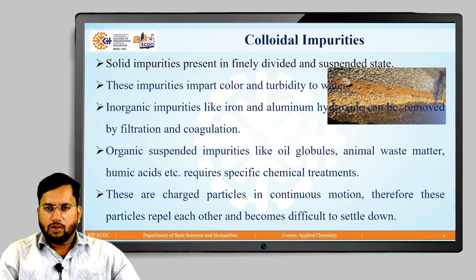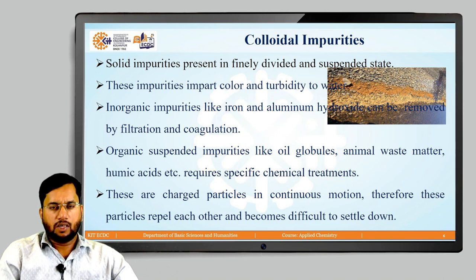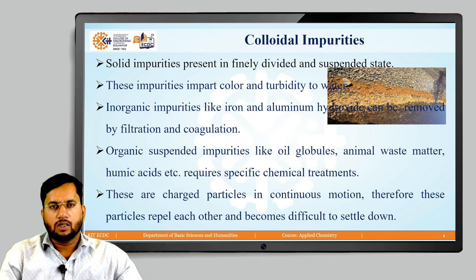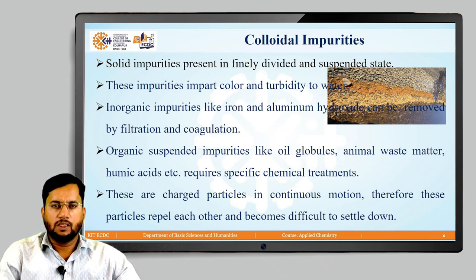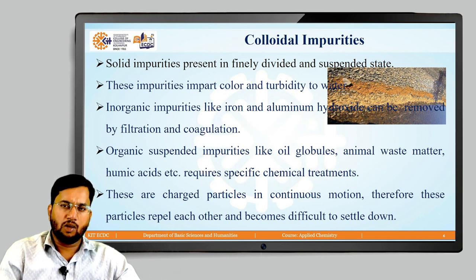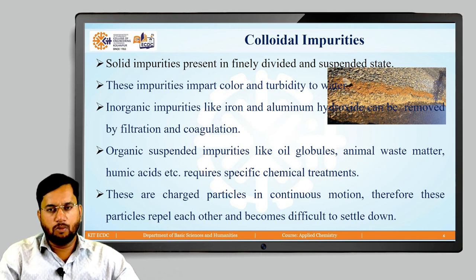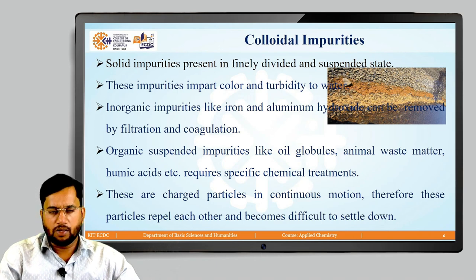Colloidal impurities are generally difficult to remove as they are charged particles always in continuous motion, making it difficult to settle them. Colloidal impurities are solid impurities present in a finely divided and suspended state, and they impart colour and turbidity to water. Inorganic impurities like iron and aluminium hydroxide can be removed by filtration and coagulation, whereas organic colloidal impurities like oil globules, animal waste matter, and humic acid require specific chemical treatment.